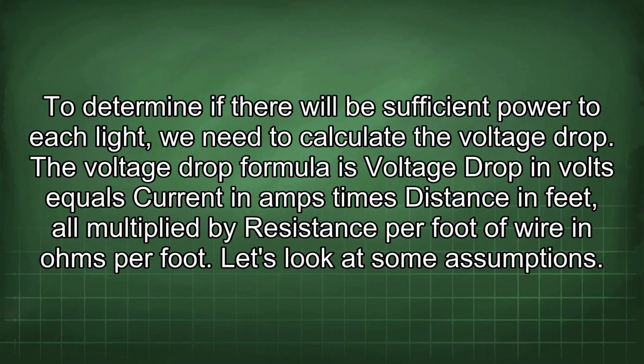To determine if there will be sufficient power to each light, we need to calculate the voltage drop. The voltage drop formula is: voltage drop in volts equals current in amps times distance in feet, all multiplied by resistance per foot of wire in ohms per foot. Let's look at some assumptions.